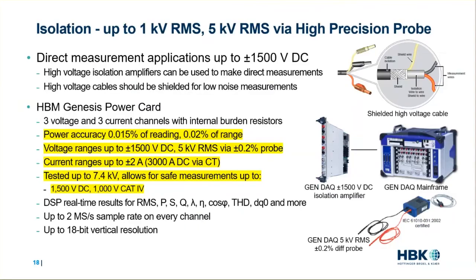Also, currents can easily be measured using the power card's internal high-accuracy burden resistors, which support all the common zero-flux current transducers. The power card has been tested up to 7.4 kilovolts, which allows for safe measurements up to 1,500 volts DC and 1,000 volts Cat4. The card offers many predefined calculations for RMS, P, S, Q, lambda, efficiency, THD, DQ0, and much more. Plus, you can also write your own custom real-time equations.